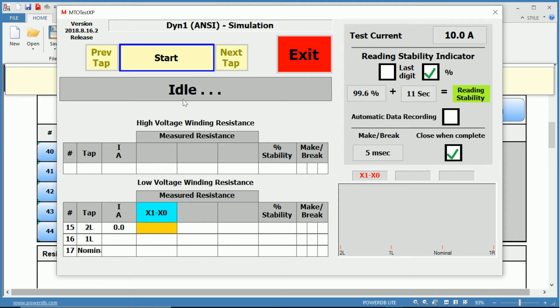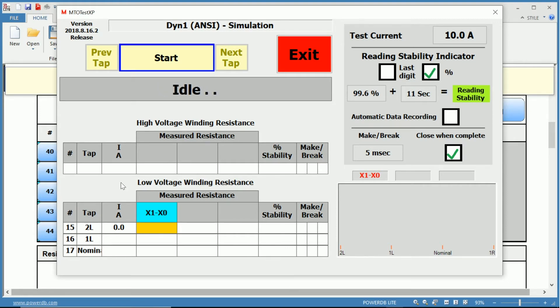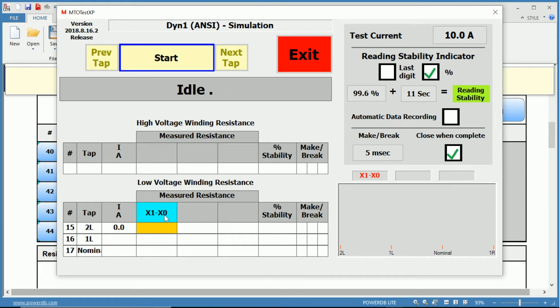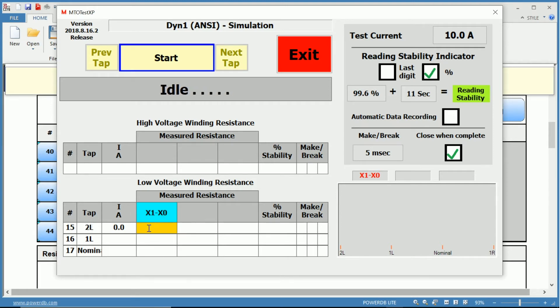Also, the updated status of the test during performing the actual measurement. Below that, you have your high voltage winding resistance, and below that, your low voltage winding resistance. Since we selected in our test selections that we wanted to test the secondary, you can notice the X1 to X0 phase illuminated in this teal box.